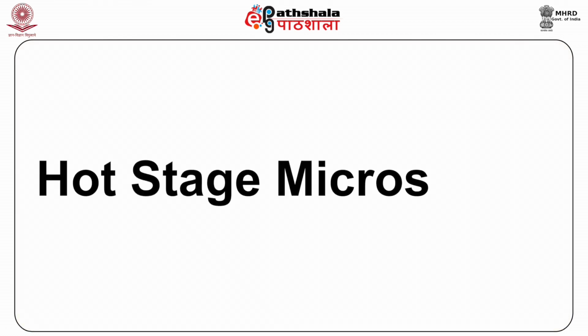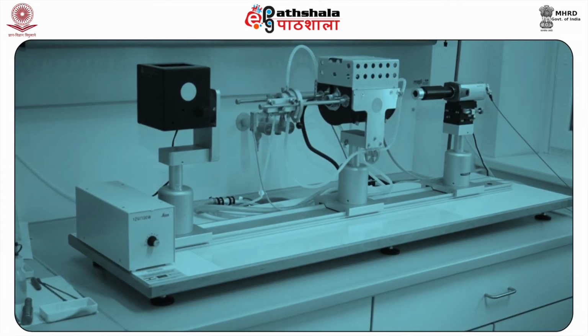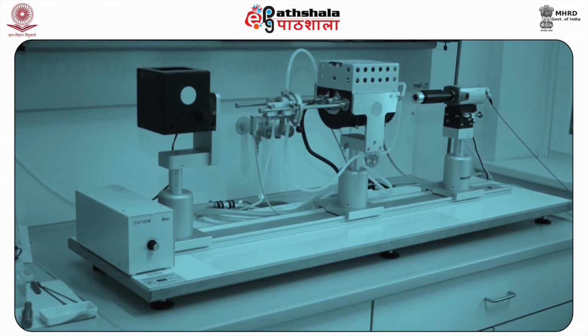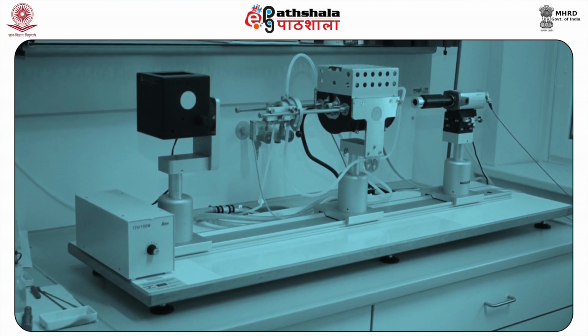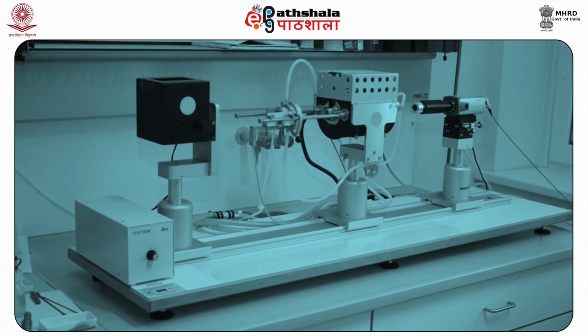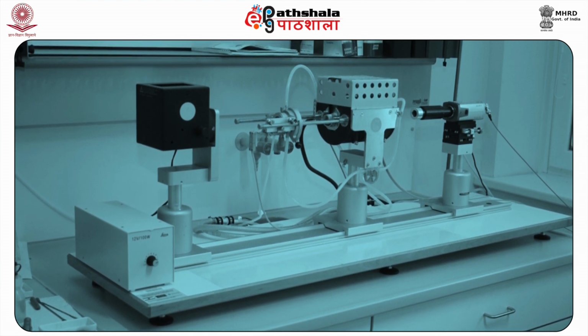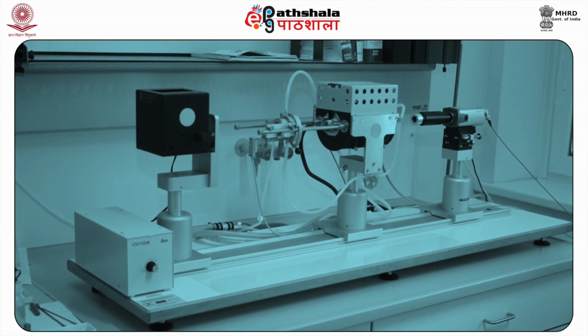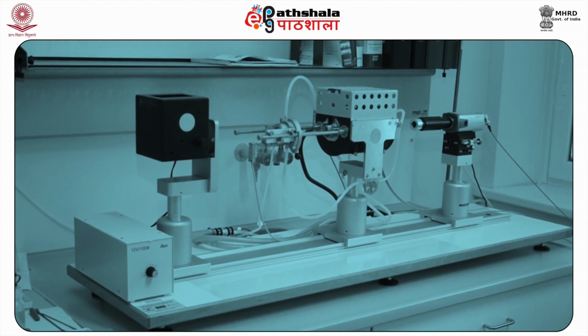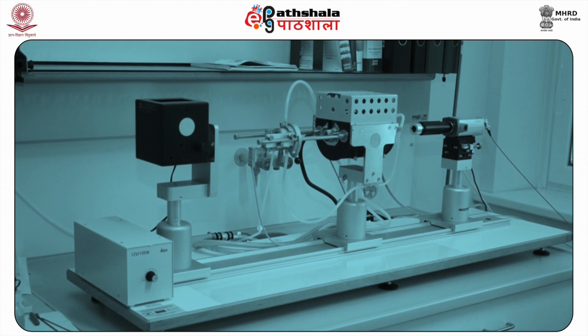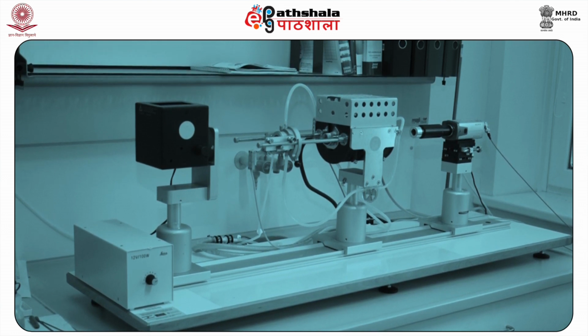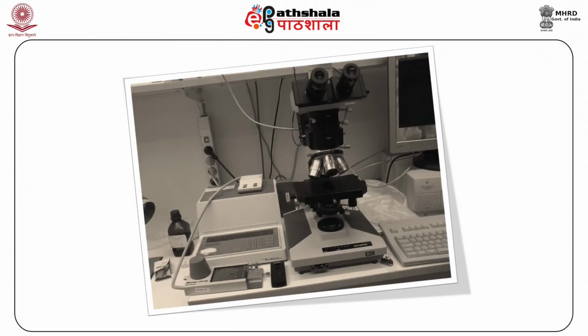Hot stage microscope. The hot stage polarizing microscope is used to study the optoelectronic and thermal behavior of liquid crystal, organic, and polymeric samples. In the heating stage, samples are positioned between a commercial slide and a cover glass. The photo monitor allows determination and plotting of the light intensity of the field of view as a function of temperature.